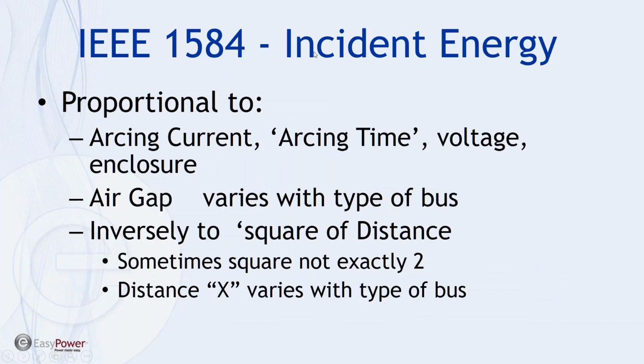Then the next topic is incident energy, and this goes to the two handouts that I presented. IEEE 1584 says the incident energy is proportional to the arcing current, the arcing time, the voltage, the type of enclosure, the air gap, and it's inversely proportional to the square of the distance. Well, at least that's the way I explain it.